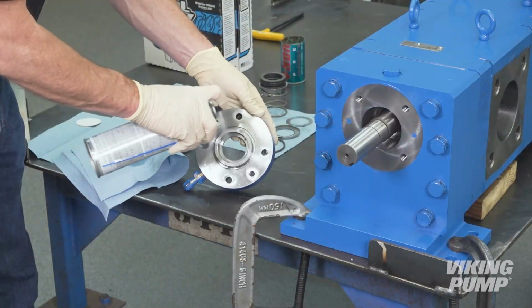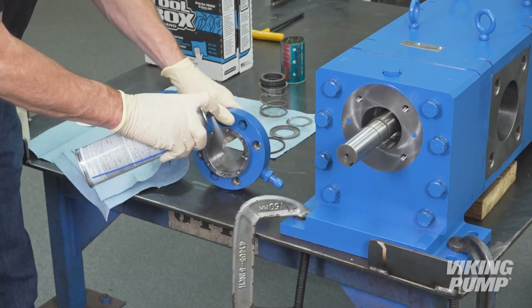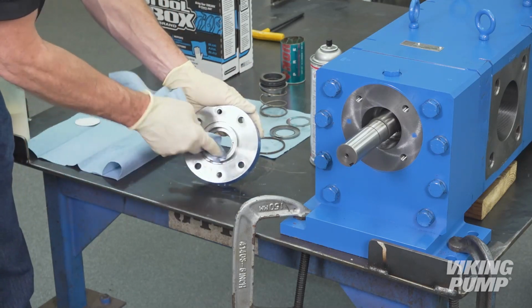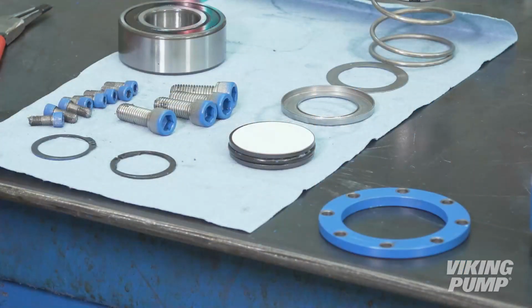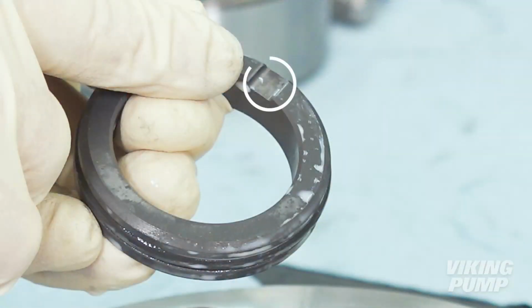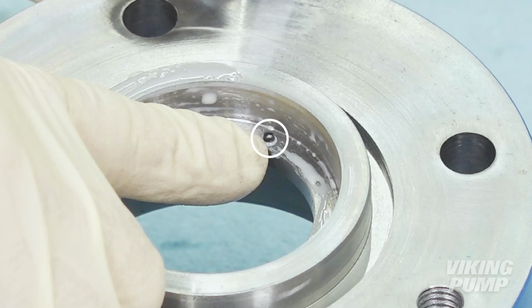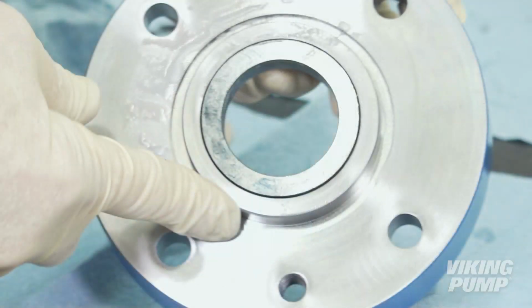It is now time for the seal installation. Begin by cleaning the seal holder assembly thoroughly. Next, install the stationary seat into the seal holder assembly. Make sure to line up the notch with the pin in the face of the seal holder assembly. Remember that the face of the stationary seat has been lapped to a mirror finish. Any damage will affect the sealing ability of the mechanical seal.